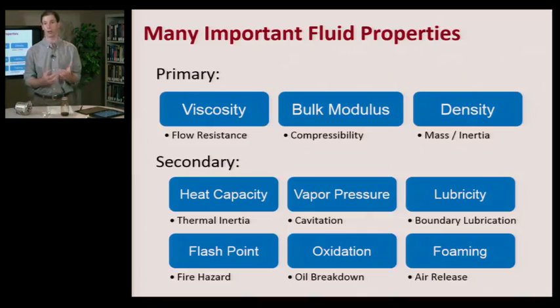And then vapor cavitation where we are compressing that vapor in our hydraulic pump and then those vapor bubbles collapse and cause micro jets which cause major component wear.